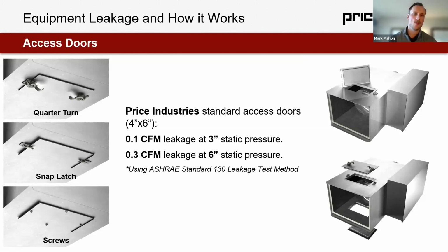But one thing I'll say with Price that we've seen is the first, second, and fifth time this access door is opened and closed is not an issue. The 50th time the door is potentially opened and closed, you can start to see some leakage deterioration because of the gasket starting to wear and break down, and potentially a contractor not putting it in fully square, or as they take it out and put it back in, starting to deteriorate that gasket.